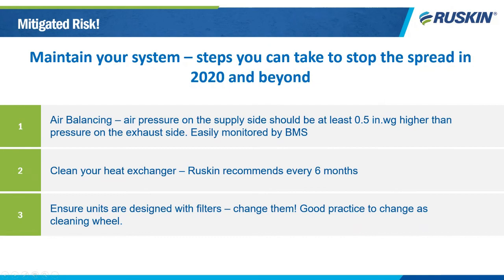Next slide. And what can you do to mitigate the risk? How are we going to stop the spread in 2020 and beyond? Some of these may be self-explanatory. However, I know we've all seen filters that have not been changed. So at step one, we say keep your system balanced. Run air balancing, okay? Go out and get these calculations done. We want the air pressure on the supply side to be at least half an inch higher than that on the exhaust side. Ruskin's units do come with an option for a pressure monitor, but pressure can easily be monitored by the BMS. So do air balancing, keep up with your system.